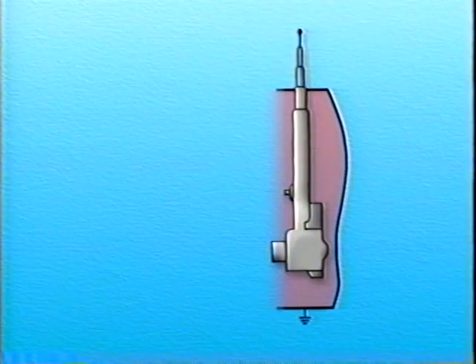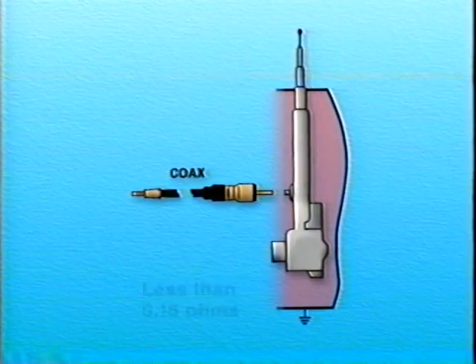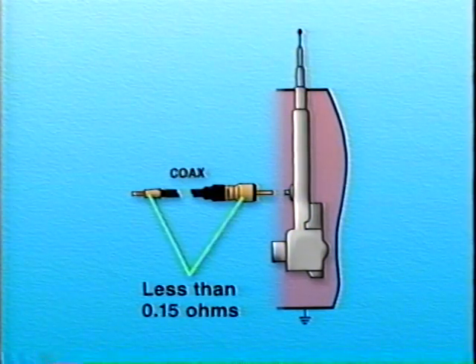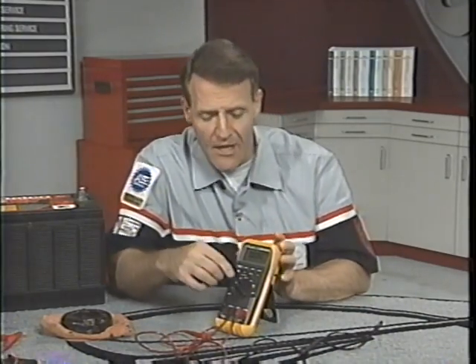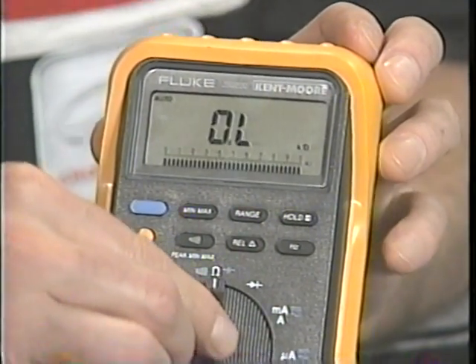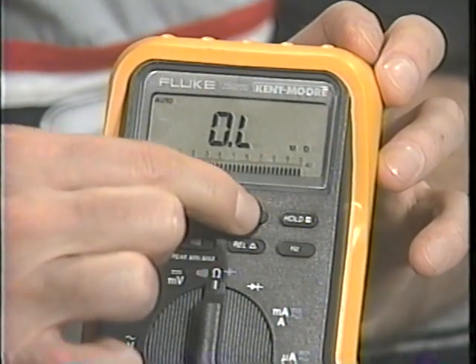These days, many antenna systems require very low resistance, both in the antenna itself and in the lead-in cable. In some cases, the spec is less than 0.15 ohms. But the meter's own leads may have more resistance than that. To remove their resistance from the picture, set the dial to ohms and press range to get out of auto range. Auto range works fine for high resistances, but for very low ones, scroll to the lowest range, which is 400 ohms.